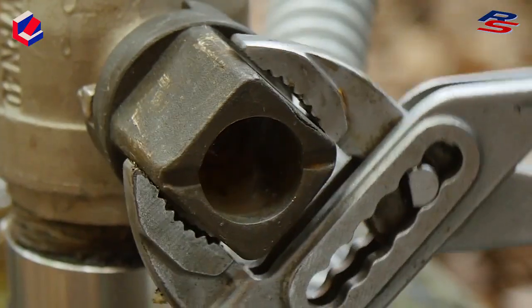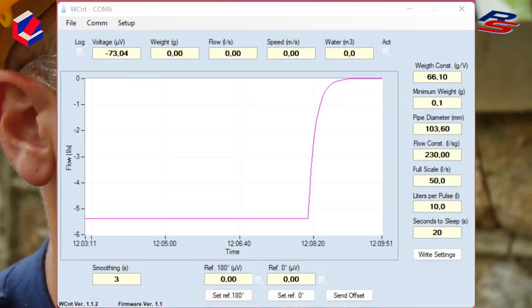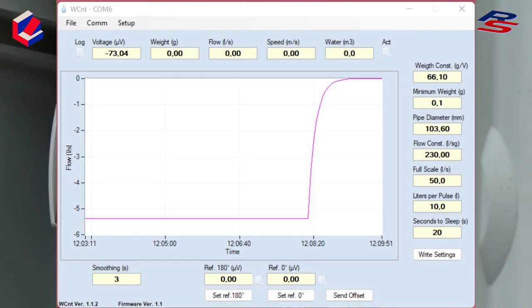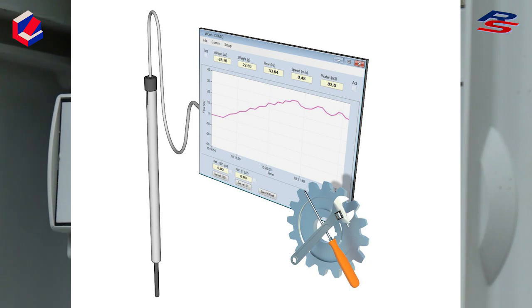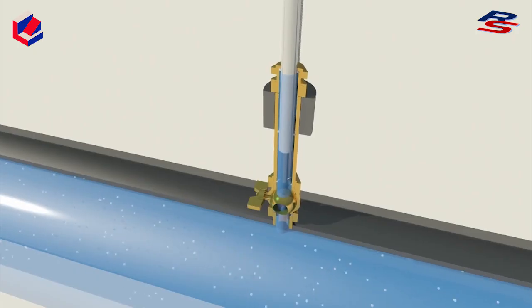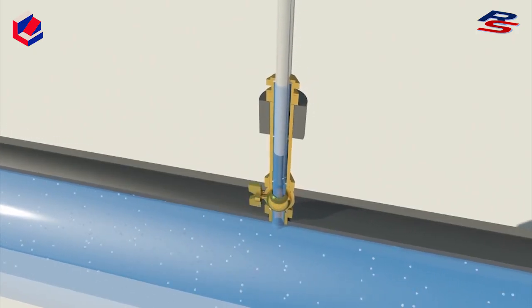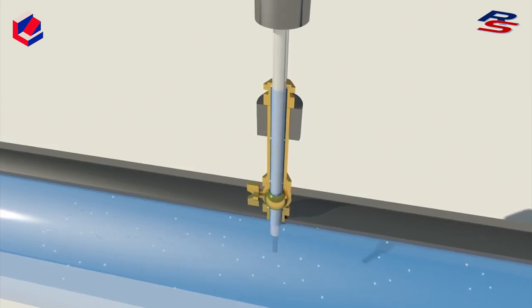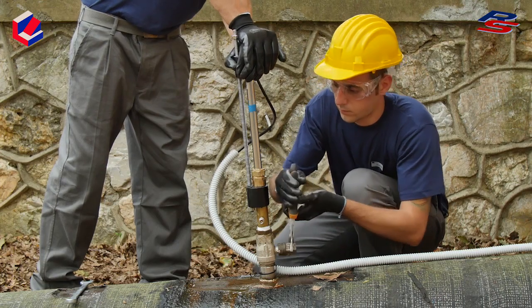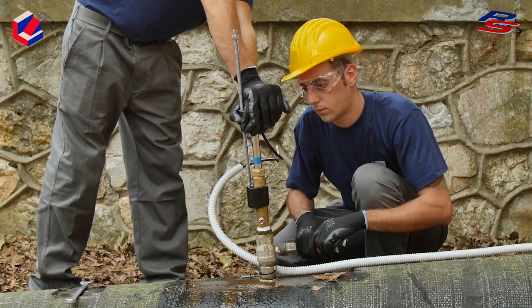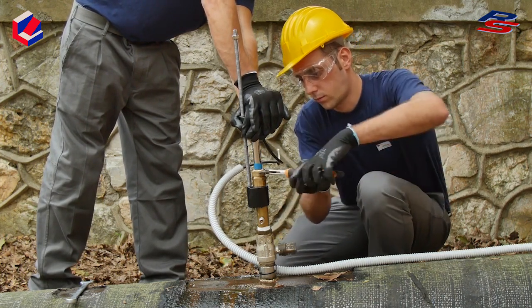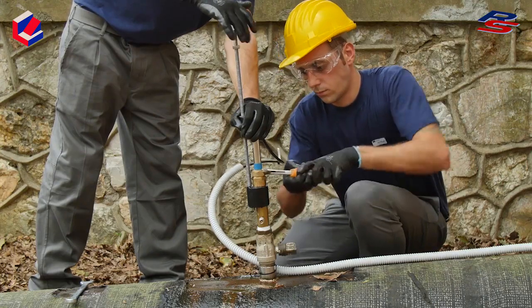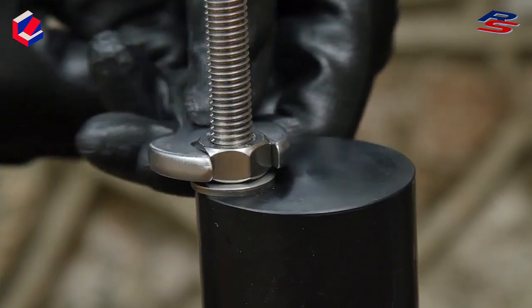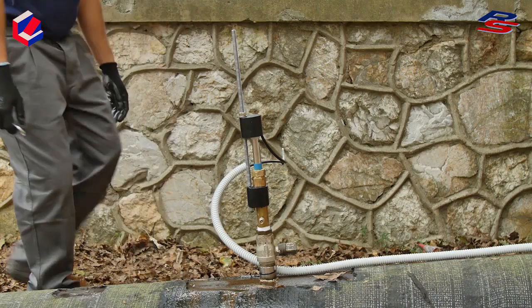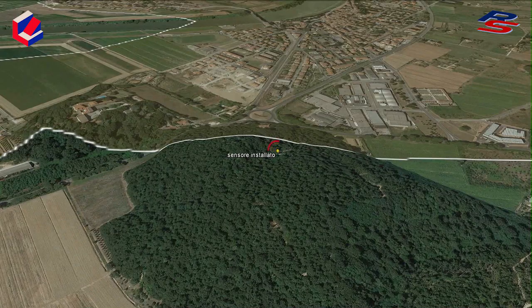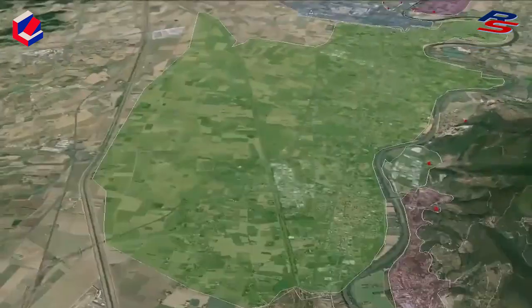Before positioning the sensor definitively in place, the elements of force must be reset to 0 so as to give the meter a null value. This can be done with a calibration software. After that, the valve can be reopened and the sensor pushed inside the pipeline to the required depth. The lock ring and safety cap can then be tightened definitively. At this point, the insertion of the sensor can be considered complete, and it will be possible to start to acquire and transmit measurements via a LoRa or NB-IoT data logger module.